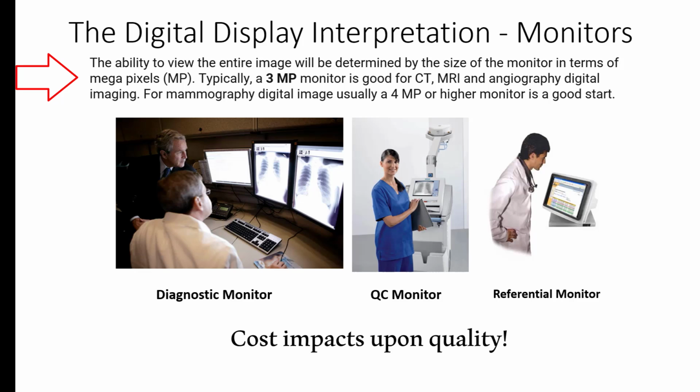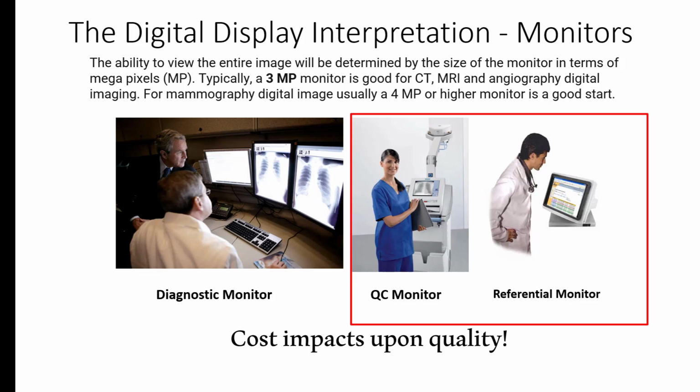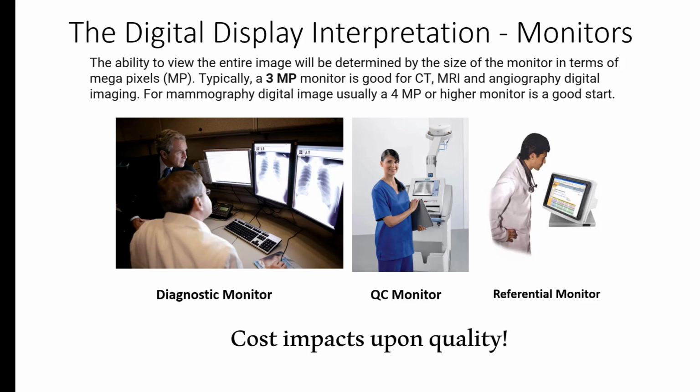The ACR recommends a 3 megapixel or greater monitor for viewing images. Now, does the QC monitor have the same resolution, contrast, and density as the radiologist monitor? Sure wish it did, but they don't. And does the referential monitor have the same contrast and density and resolution as a QC monitor? Probably not. Close, but probably not.